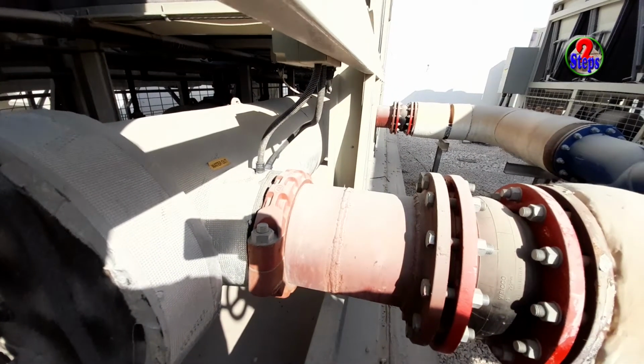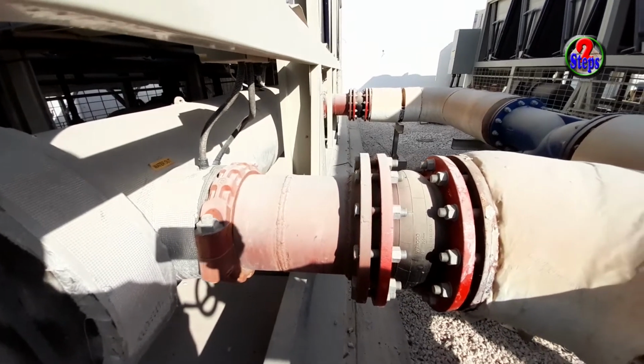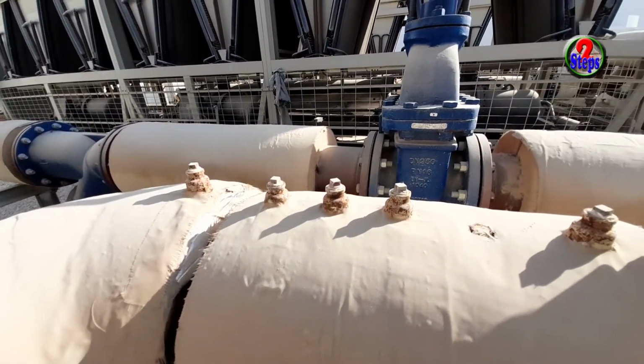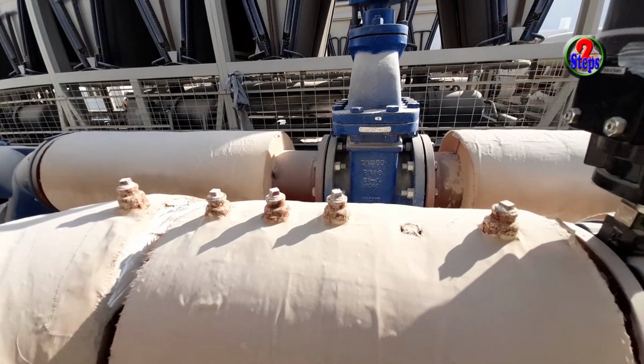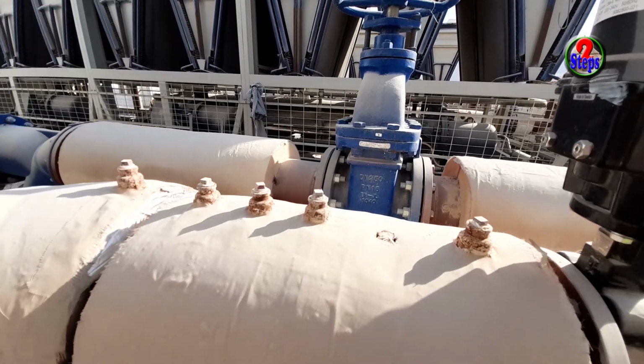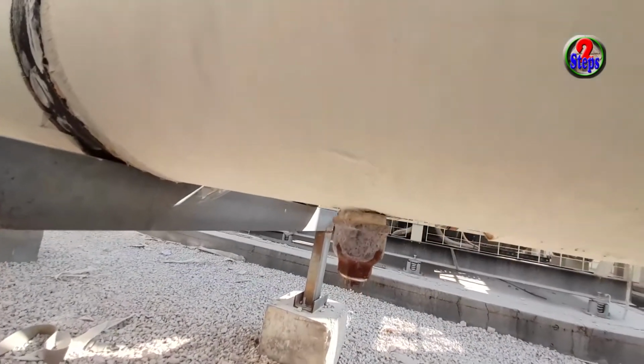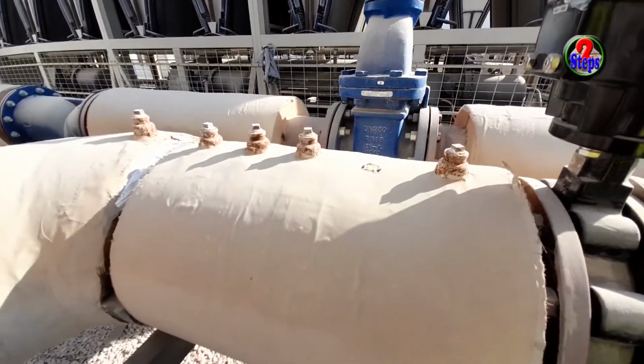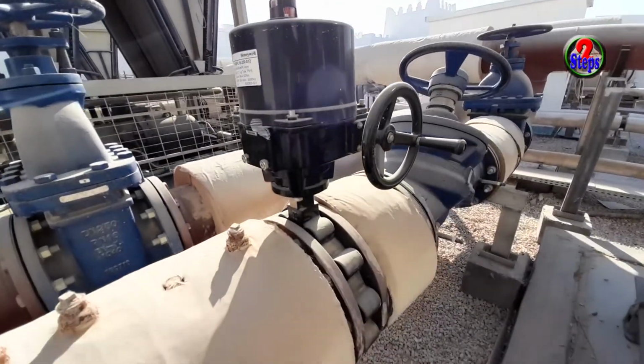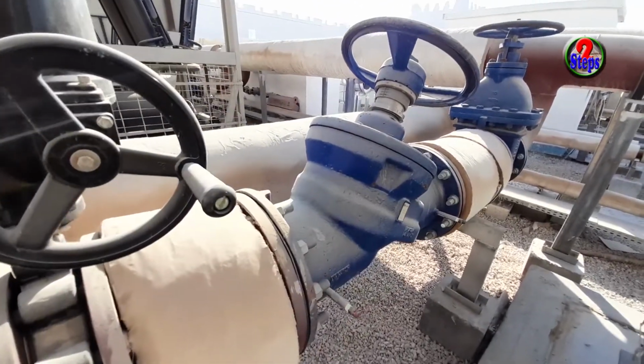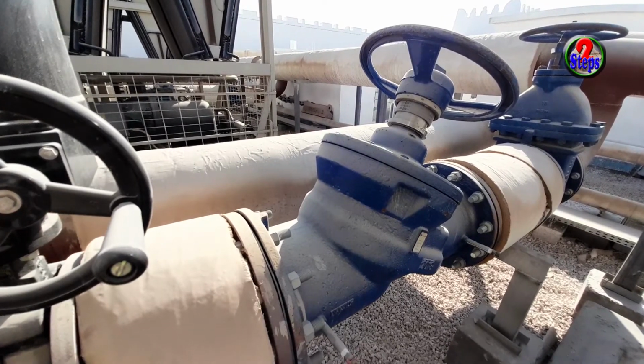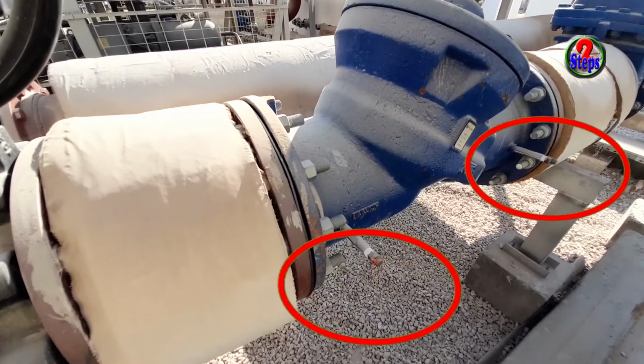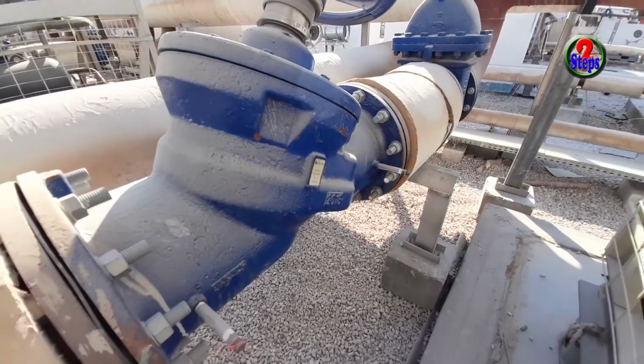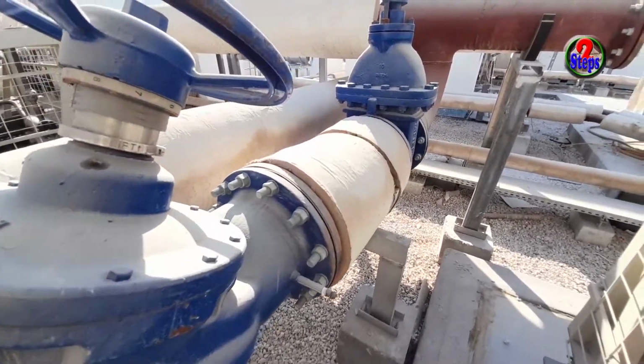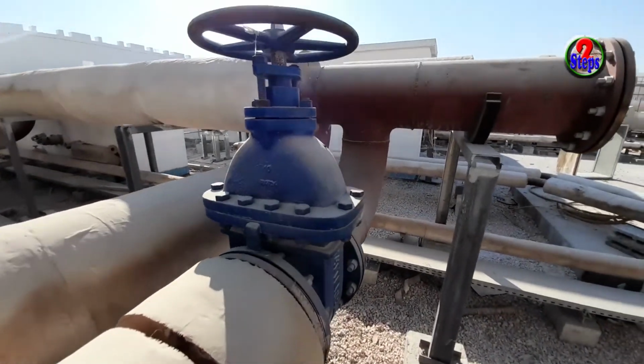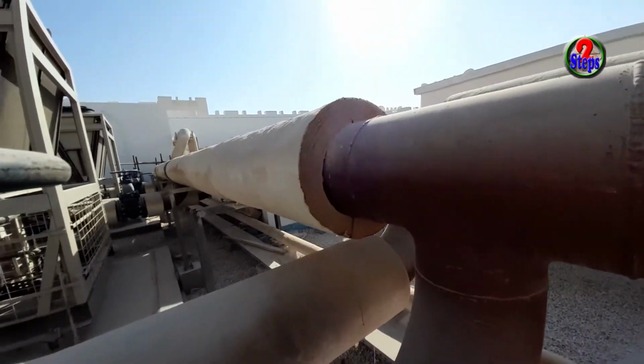This is the chiller outlet connection. Same as inlet connection, here also have a flexible connector. These are some points for automatic air vent, pressure gauge, flow switch, temperature sensor and thermostat. Bottom of the pipe also has another drain point. This is the motorized valve. After that, DRV. DRV means double regulating valve. There are two test points on both sides of the DRV. Then the isolation valve at the end connected to the chiller outlet header that goes to the secondary pumps.